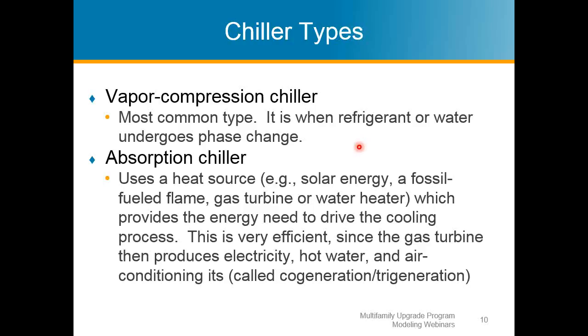But basically, it's using a heat source, such as solar energy, fossil fuel flames, gas turbines, or water heaters, and that provides the energy you need to drive the cooling process. So it's a very efficient way to do that, and sometimes you get into calling them cogens or trigens, where you have byproducts of that one system. You can have a gas turbine that provides electricity, hot water, and air conditioning. Then it's what you call a cogen or a trigen, depending on how many different things that one item is producing.